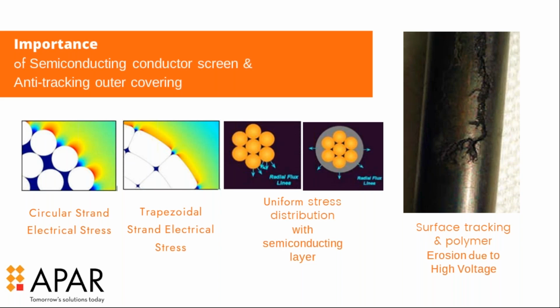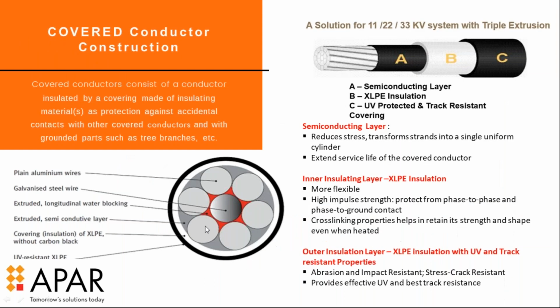Now going back to the construction, unlike the UG cable or AB cable, basically we don't have any earthing provision in this design. So if there is no earthing, there must be some leakage of current over the surface. According to the standard, this leakage current should be less than 1 milliamp. And once that is so, that means there is some voltage present, and there is some leakage of current. So the voltage should be less than 100 volts in the 11 kV circuit network.